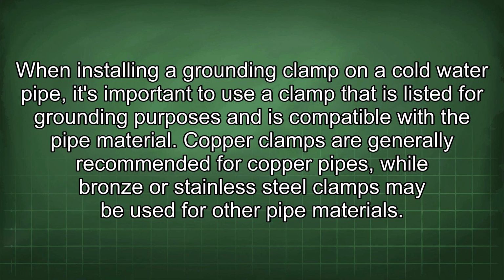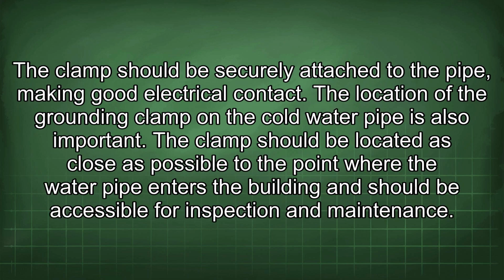When installing a grounding clamp on a cold water pipe, it's important to use a clamp that is listed for grounding purposes and is compatible with the pipe material. Copper clamps are generally recommended for copper pipes, while bronze or stainless steel clamps may be used for other pipe materials. The clamp should be securely attached to the pipe, making good electrical contact. The location of the grounding clamp on the cold water pipe is also important. The clamp should be located as close as possible to the point where the water pipe enters the building and should be accessible for inspection and maintenance.